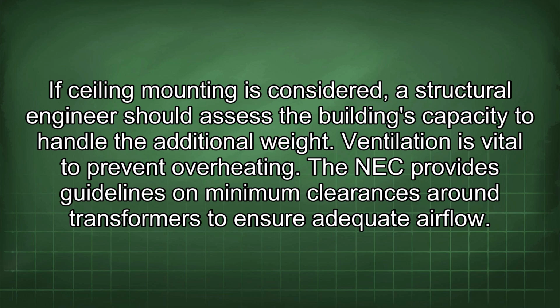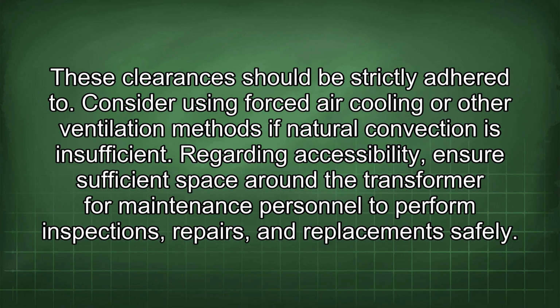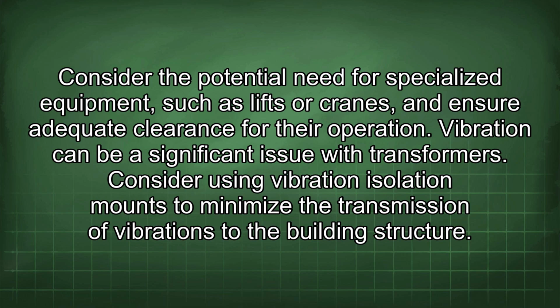Ventilation is vital to prevent overheating. The NEC provides guidelines on minimum clearances around transformers to ensure adequate airflow. These clearances should be strictly adhered to. Consider using forced air cooling or other ventilation methods if natural convection is insufficient. Regarding accessibility, ensure sufficient space around the transformer for maintenance personnel to perform inspections, repairs, and replacements safely. Consider the potential need for specialized equipment, such as lifts or cranes, and ensure adequate clearance for their operation.